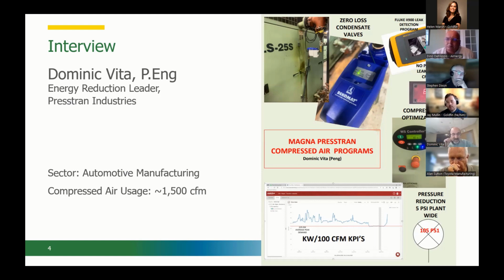Well, the first chance I got when I started early in March this year was to come in on a weekend, and of course on the weekend you get some special opportunities to find energy opportunities—there's not X number of robots working and moving, and fork trucks driving, so you can walk around freely and make note. One of my visits was in the compressor room, and we had some quite big three-cell compressors, 350 and 300 horsepower, so there was over 1,000 horsepower there. And of course, as an energy engineer, that triggers a few things.